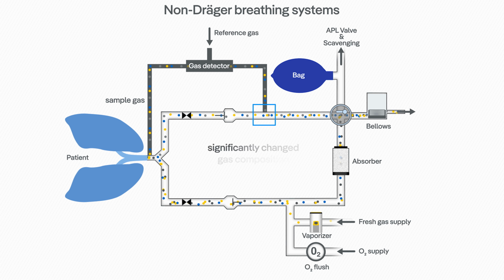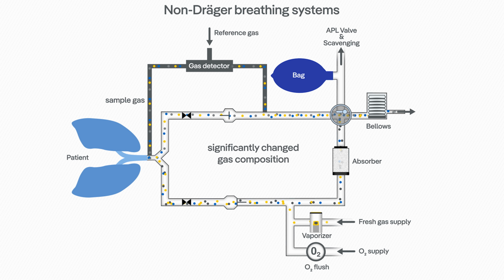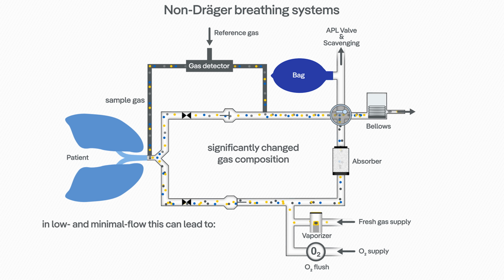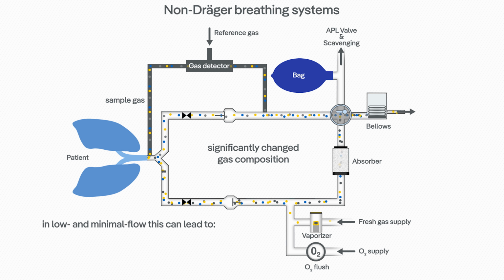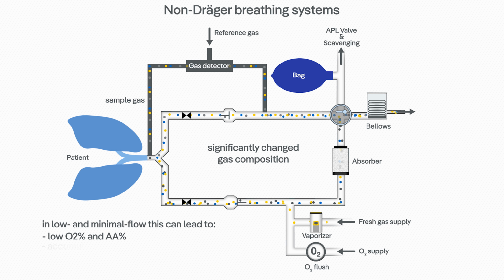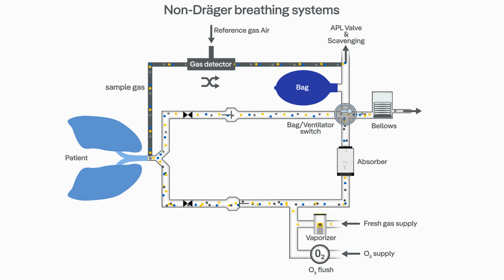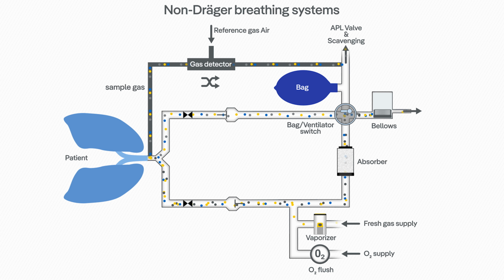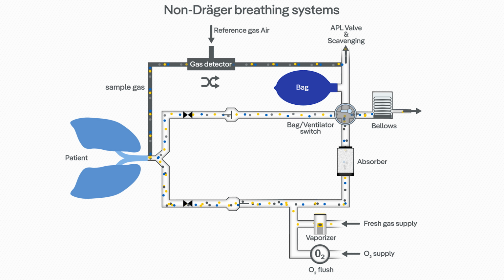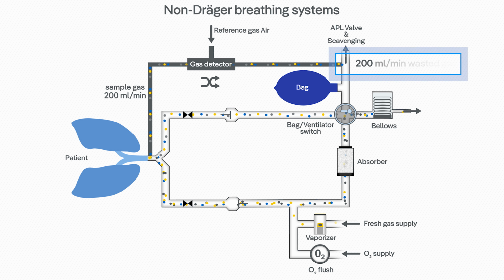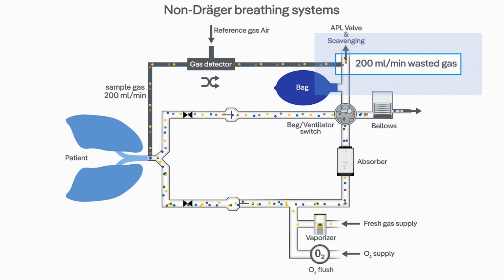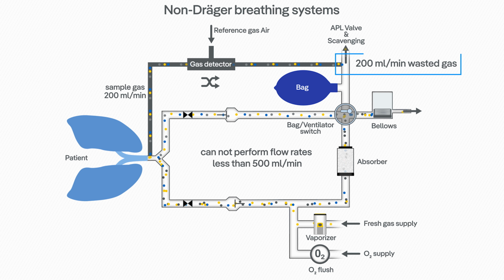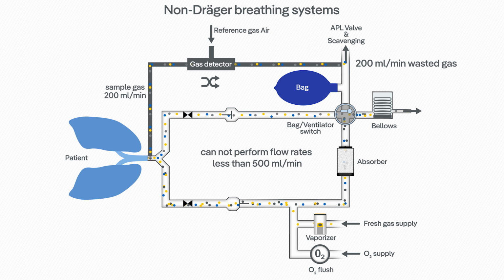Therefore, returning this sample gas to the breathing system can significantly alter the gas composition within the breathing system. Especially in low and minimal flow anesthesia, it may lower the portion of oxygen and anesthetic agent and accumulate nitrogen in the entire breathing system. Due to this issue, some devices utilizing this sensor technology may not return sample gas back into the breathing system. However, not returning the sample gas, which is usually approximately 200 milliliters per minute, means a systematic leak of significant magnitude. That's why these devices are not able to operate at flow rates of less than 500 milliliters per minute.